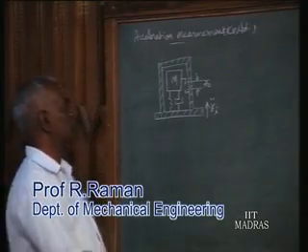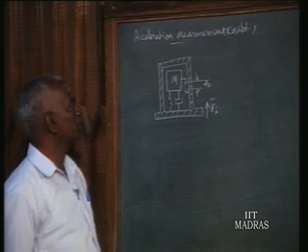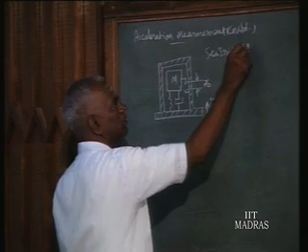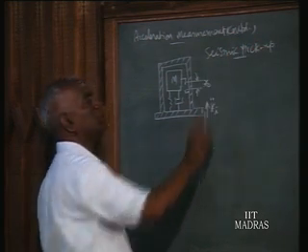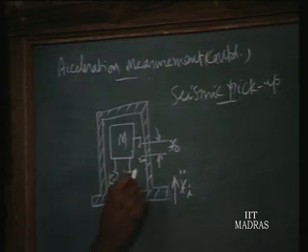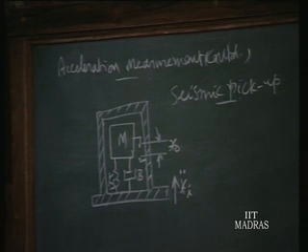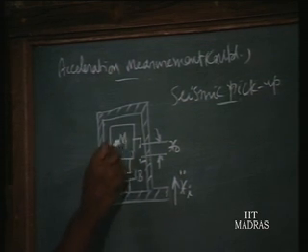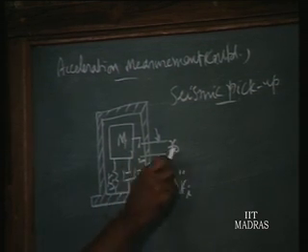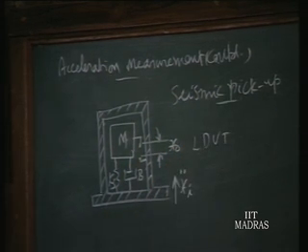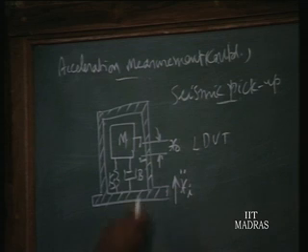Now, we have seen the theory of operation of an accelerometer — that is, a seismic pickup used as an accelerometer. In this, the main construction is a mass supported by a spring with spring constant K_s and a damper with damping coefficient b. By measuring x_o, the relative displacement of the mass with reference to the frame of the instrument, using an LVDT or any other displacement measuring instrument, and calibrating that reading in terms of input acceleration — that is what we derived from the theory.